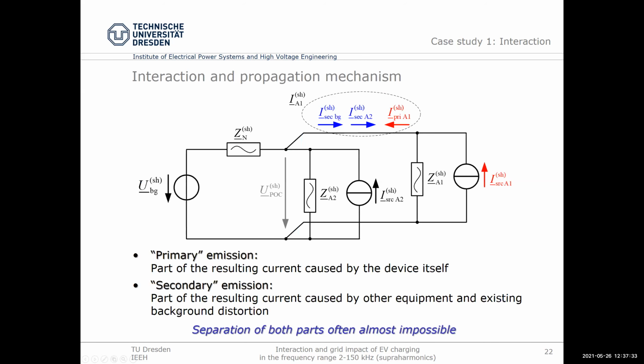This is basically due to the interaction of the different impedances. The impedance situation in this frequency range is very different compared to what we usually expect in the harmonic range, assuming no resonance. There we usually say the network impedance is much lower than the impedance of the individual connected devices, so you can roughly say it's like a constant current source. In the frequency range above 2 kilohertz, this basically doesn't hold true anymore, because the impedance situation is qualitatively completely different - normally in that range the network impedance is higher than the input impedance of the different devices.